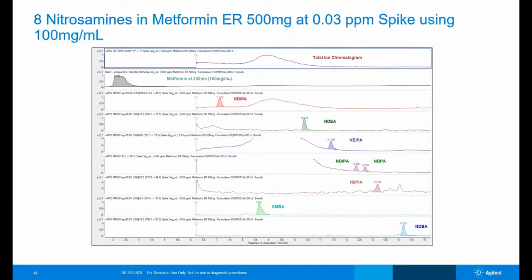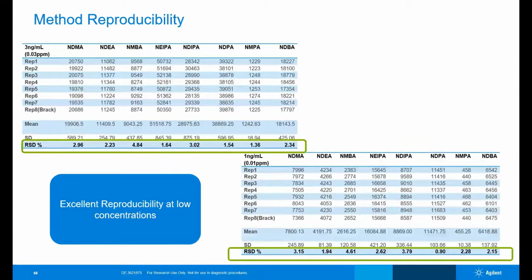Here is the method reproducibility data at 2 different concentrations. We tried to do it at 1 nanogram per ml as well as at 3 nanogram per ml, or I can say at 0.01 ppm and 0.03 ppm concentration levels. And we did this using 8 replicates, which included bracketing standard also. And you can see the reproducibility values of less than 4% or 5% in all the cases, which gives a lot of confidence in our result. And when customers run their long batches, we have the confidence that they would be able to reproduce the results, keeping in mind this type of reproducibility data.